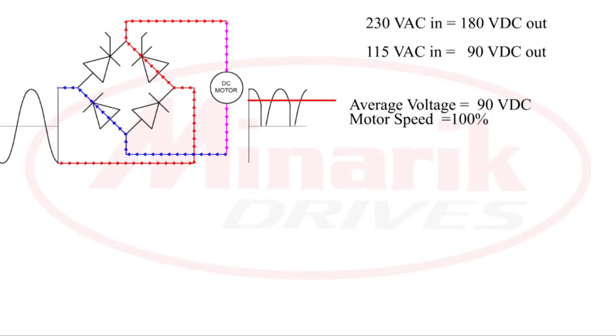If we fire the SCRs at their maximum firing angle with a 115 volt AC line, SCRs are rated for an output of 90 volts DC. With a 230 volt AC line, the output is 180 volts DC.